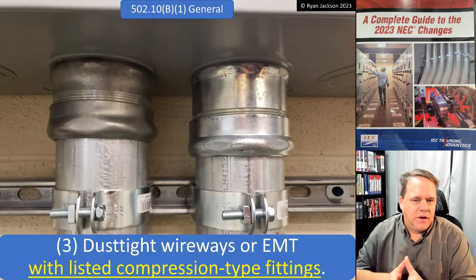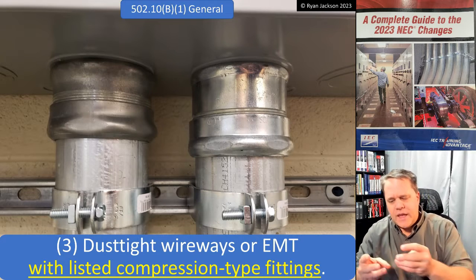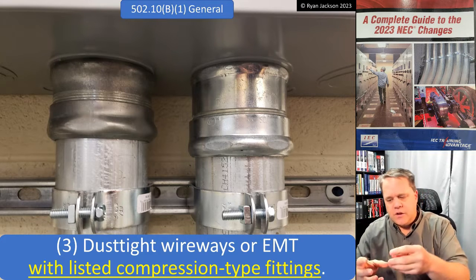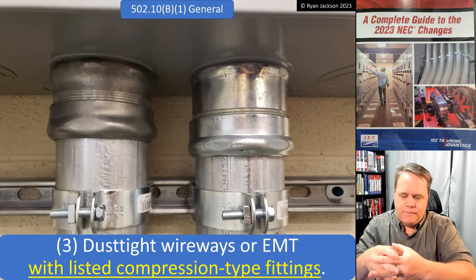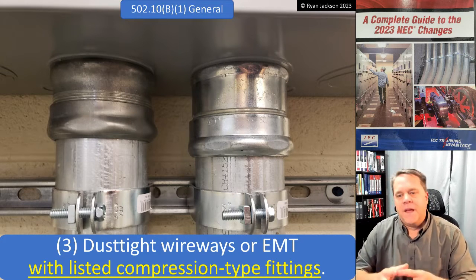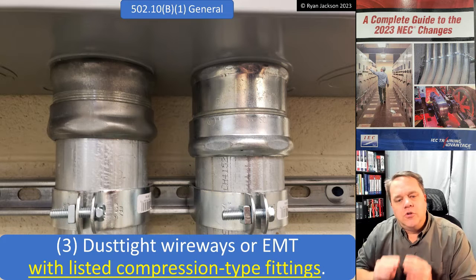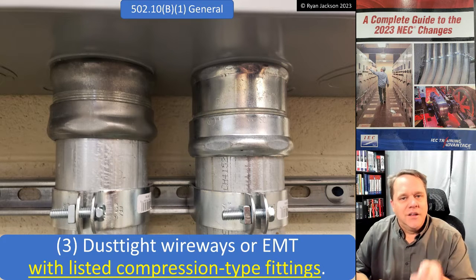The real change is that we cannot use set-screw type fittings — we have to use compression-type fittings. The issue here is the entrance of combustible dust; dust is 500 micrometers or smaller, so it's much less likely to intrude if the couplings and connectors are compression type rather than set screw type. New to this version of the code: if you want to use EMT in a Class 2 Division 2 location, that's perfectly fine, but you must use compression-type fittings, not set-screw type fittings. See you on the next video.